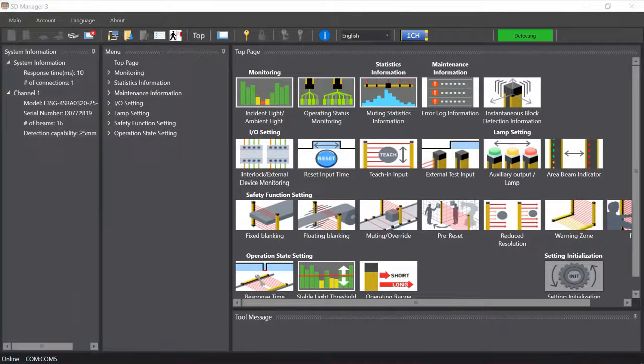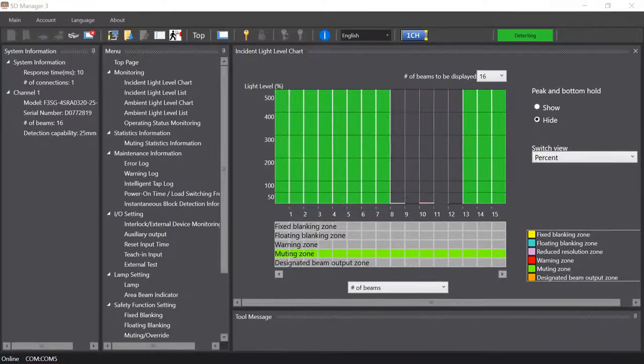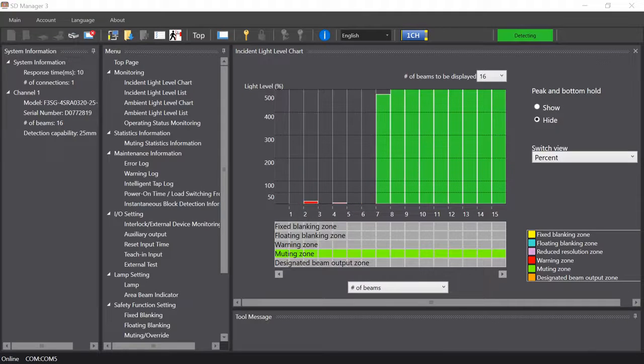Here, one can analyze real-time information from the connected light curtain. For example, the incident light level chart shows beam strength, which can tell an operator if a beam is weakened — potentially by dirt or heavy dust — or totally obstructed by a foreign object.